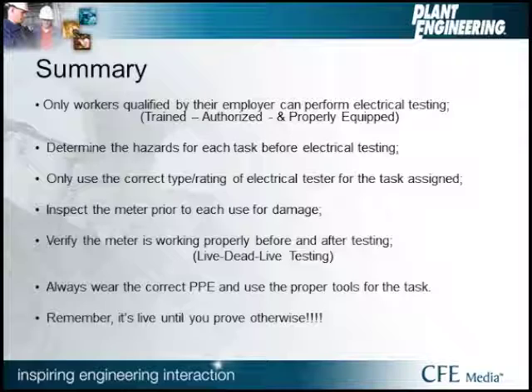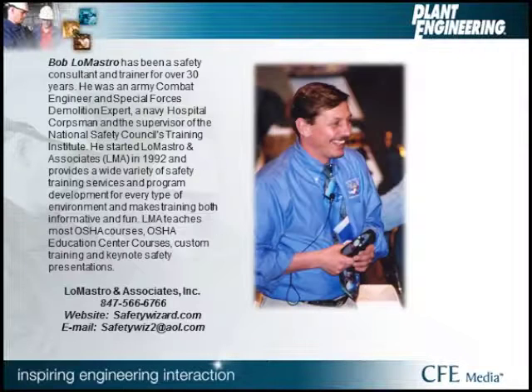Inspect your meter prior to every use for damage. Verify that it's working properly before and after your test by doing the live-dead-live testing. And always wear the correct PPE. I understand many times it seems inconvenient, but the potential hazard is life or death. And remember, it's always considered live until you can prove otherwise with a contact test.